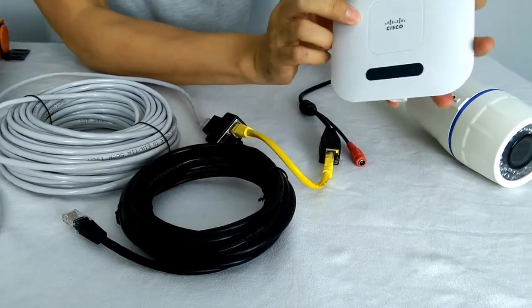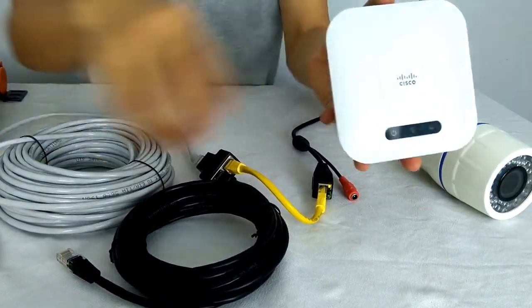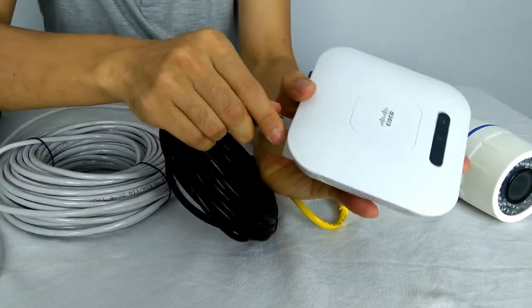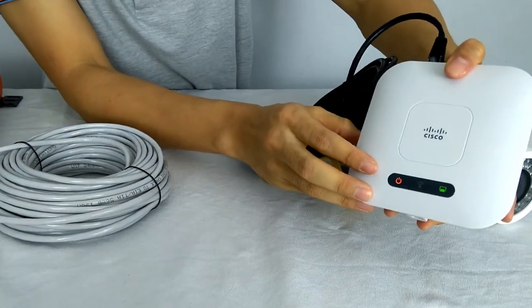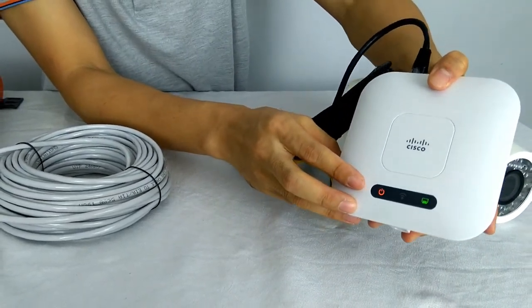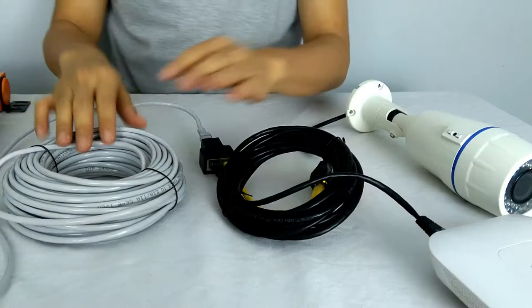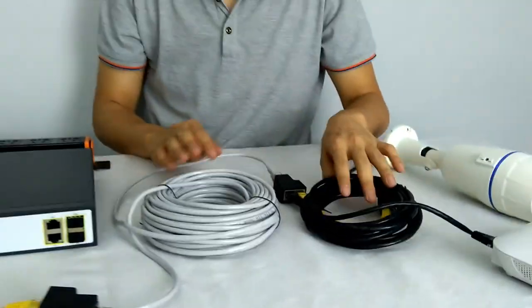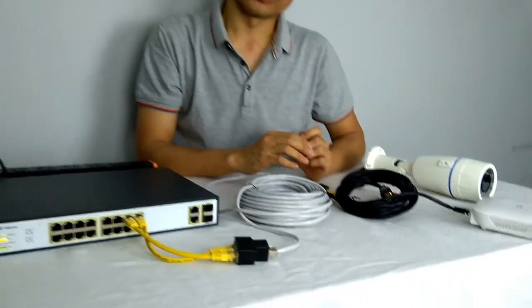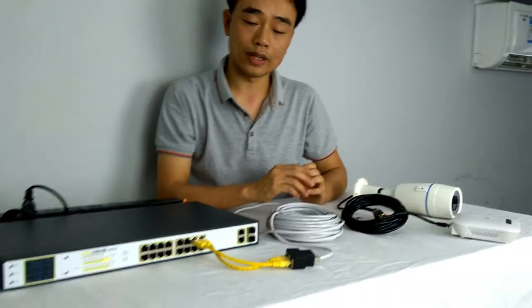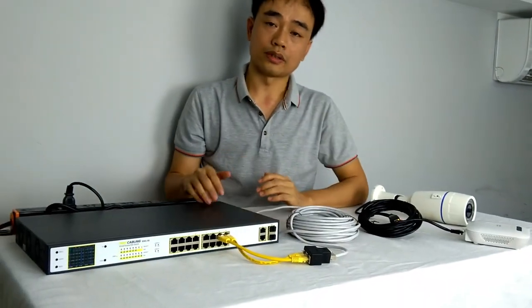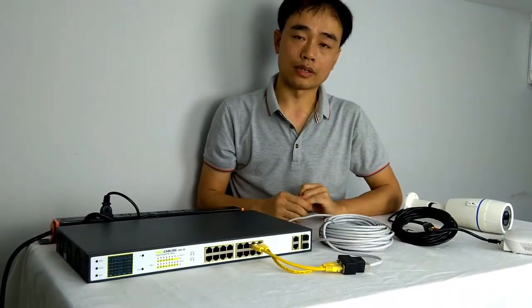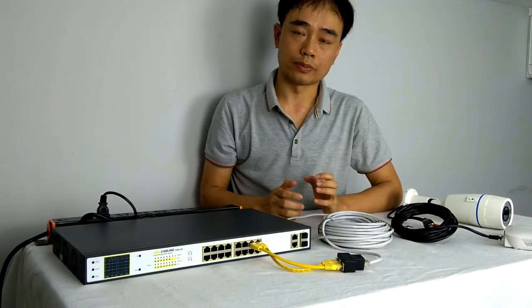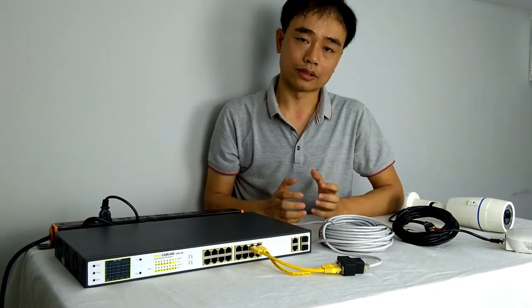This is the Cisco PoE access point. So we connect to the new access point. It's getting the power and the network. Here we're using a single internet cable to power both PoE network devices. Just beware, not all PoE devices support this way, such as the PoE NVR and PoE injector. It doesn't work this way because it needs the spare pairs to send the power.